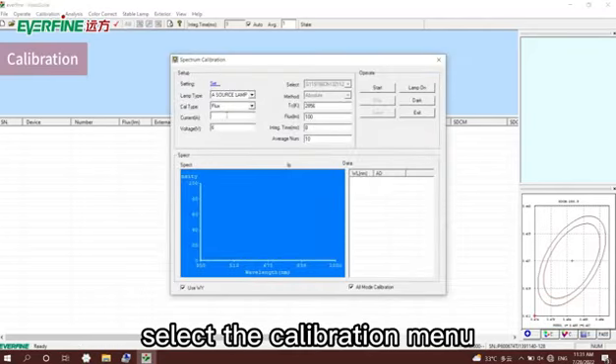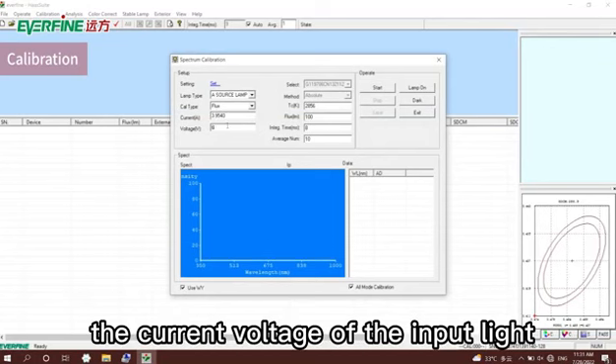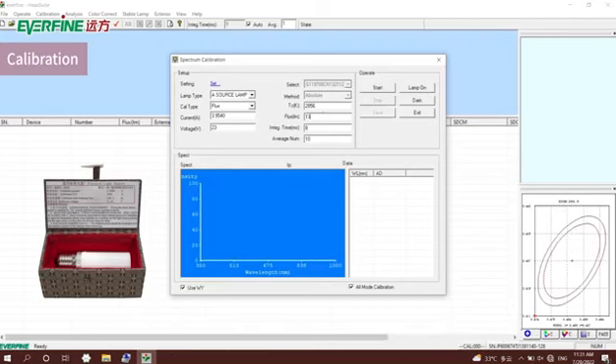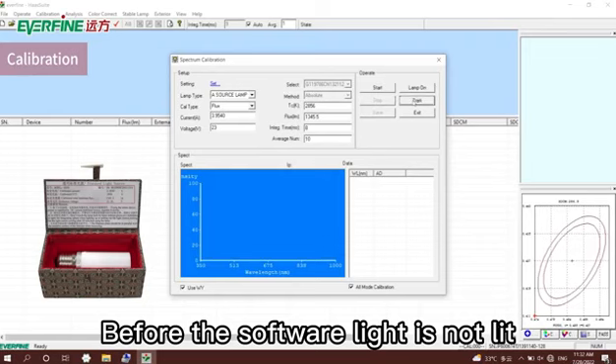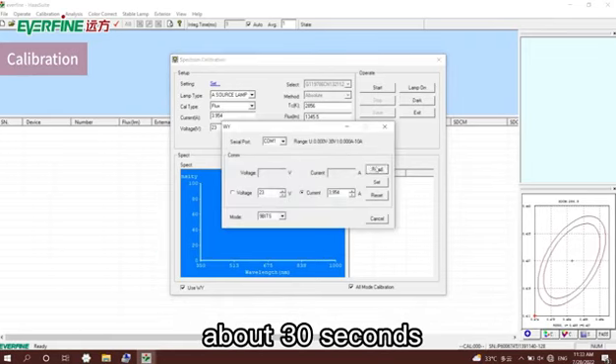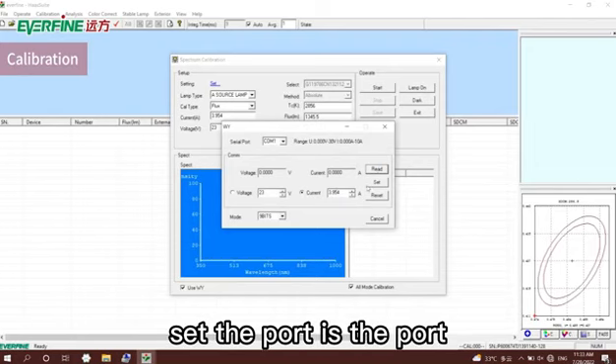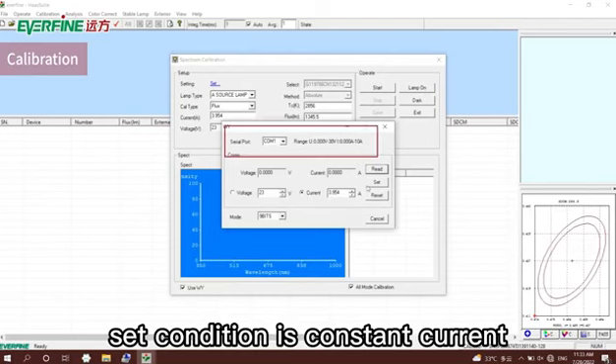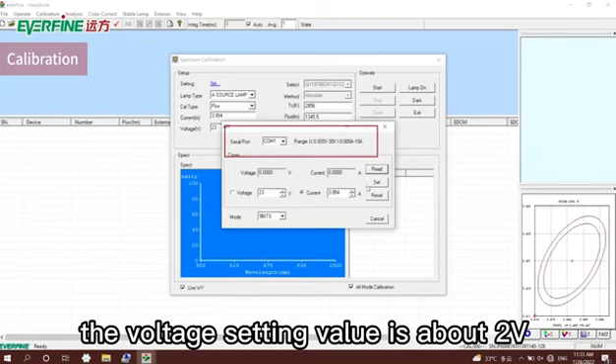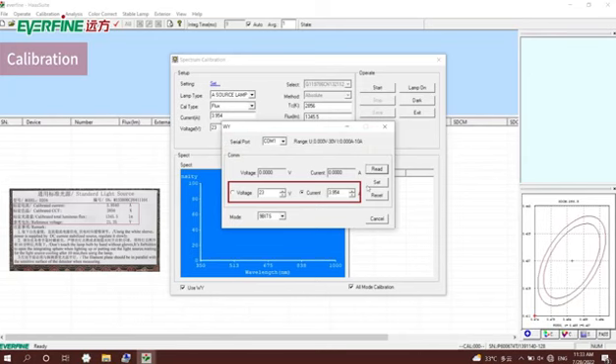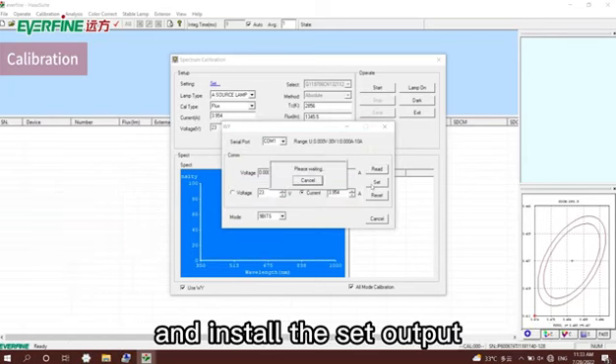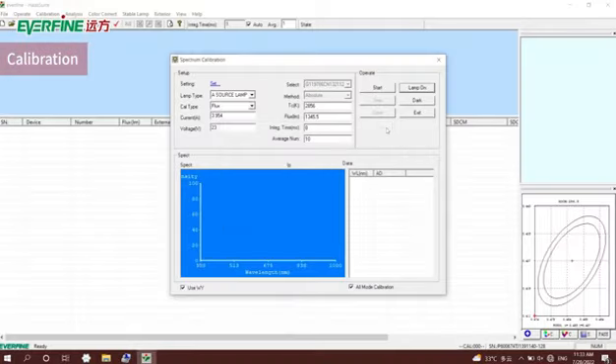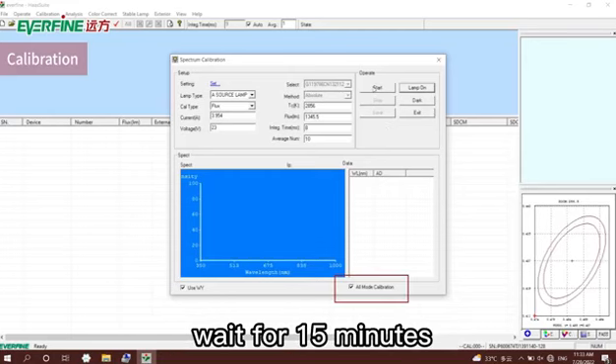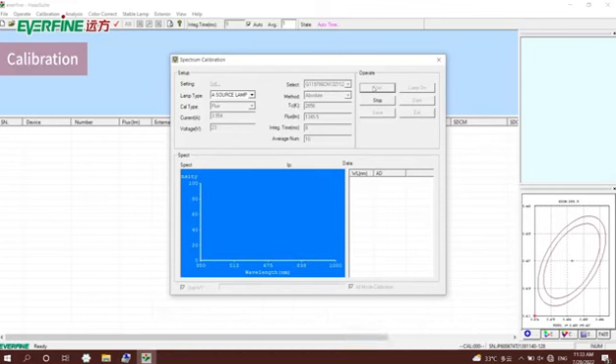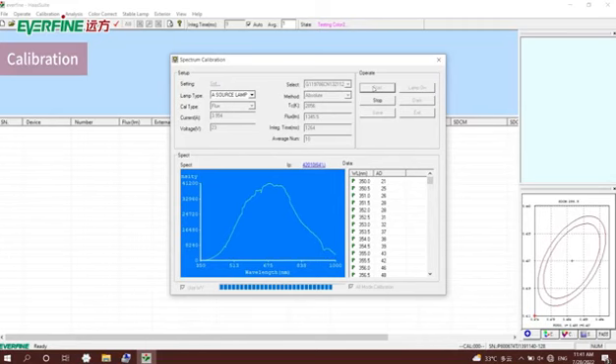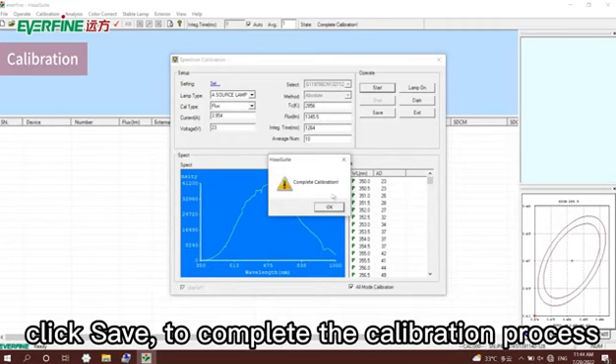Open the software, select the calibration menu, then spectrum calibration, and input the current, voltage, color temperature, and luminous flux of the lamp. Before the lamp is lit, click the Dark button to take the dark current, which takes about 30 seconds, then click the Light button. In the pop-up dialog box, set the port, such as COM1 mode, set the condition to constant current, and enter the standard lamp identification value. The voltage setting value is about 2V above the reference value. Then click Setup. The power supply will turn on the output and light up the standard lamp. At this time, exit the setting interface, light the standard lamp, and wait 15 minutes. Check all modes for calibration and click start. The system will start automatic calibration and complete it. After completion, click Save to complete the calibration process.